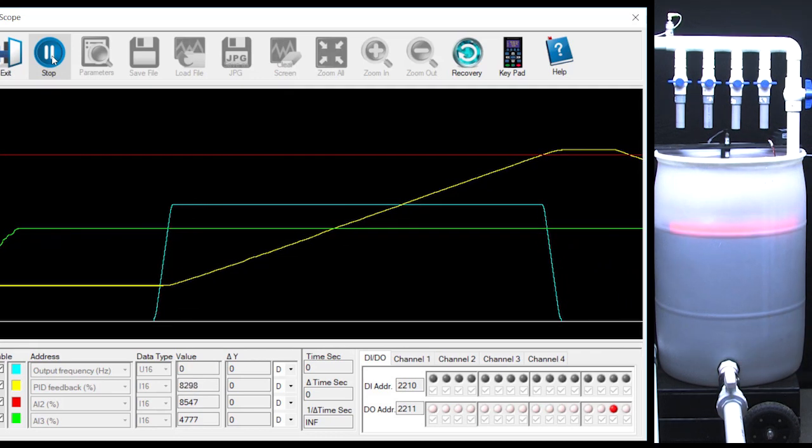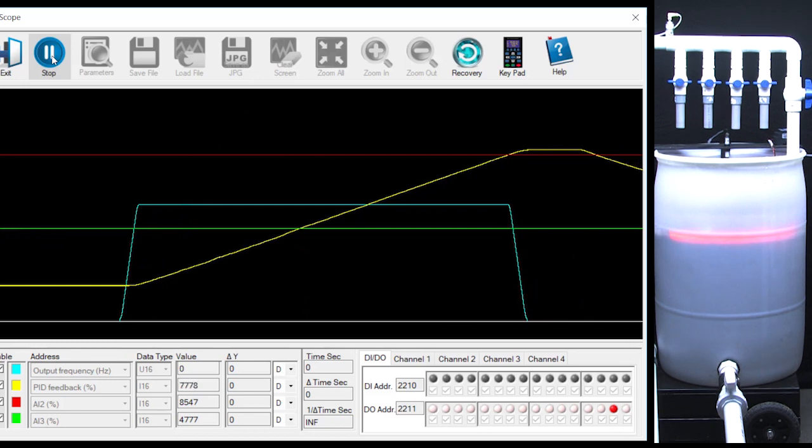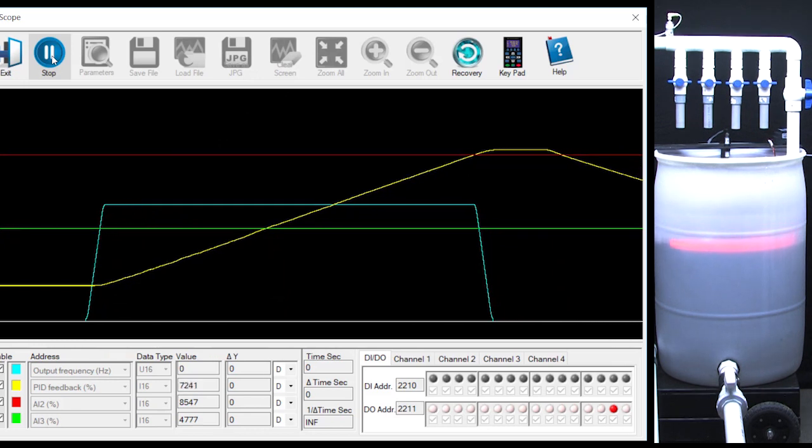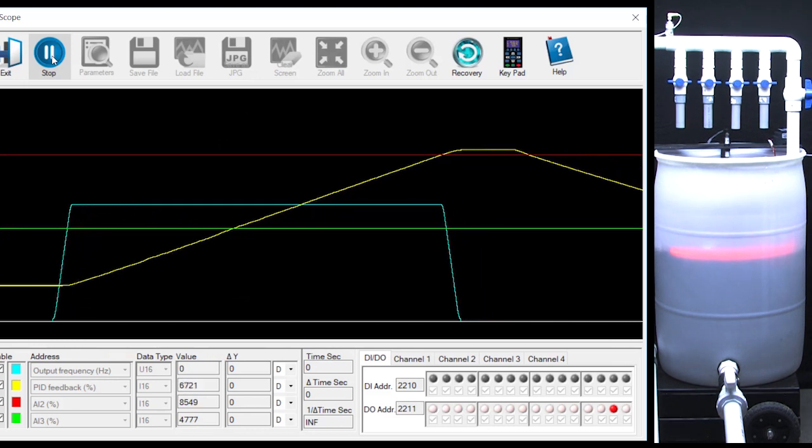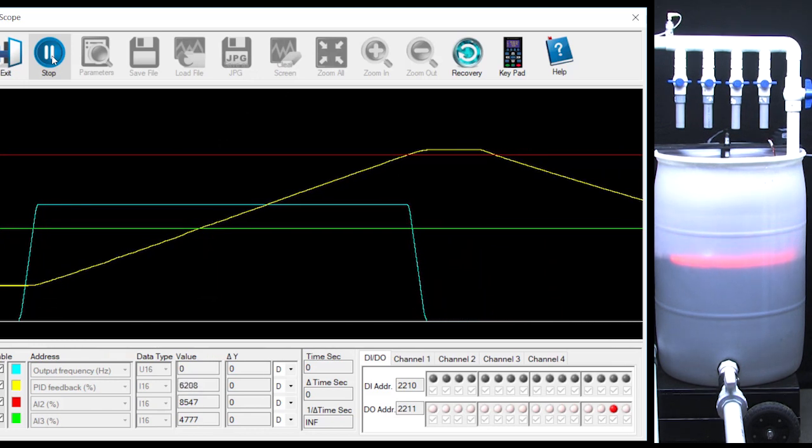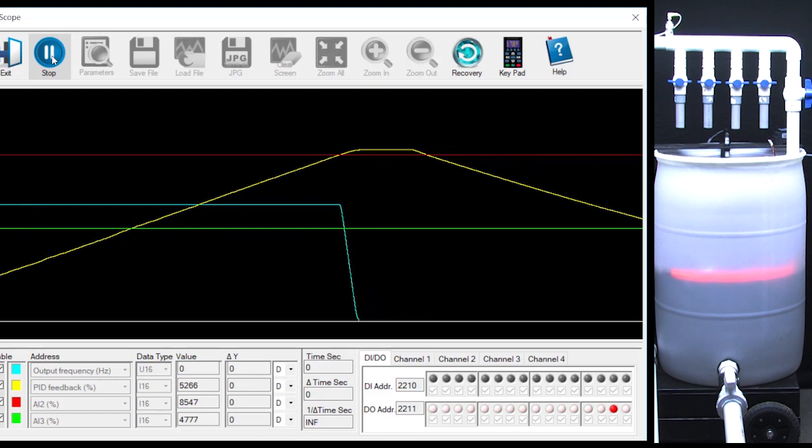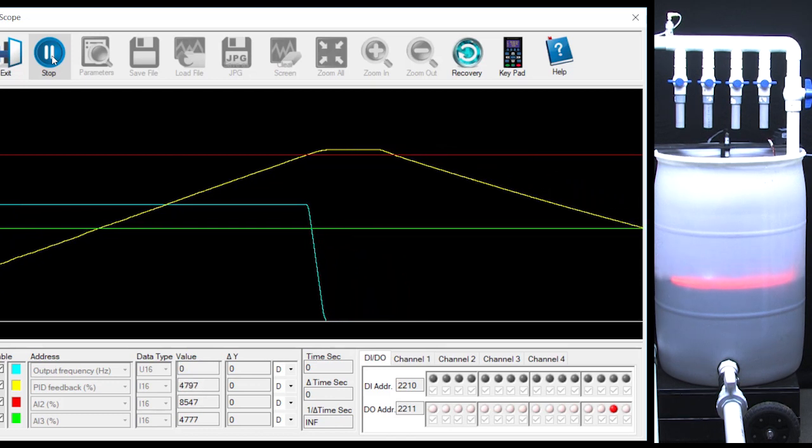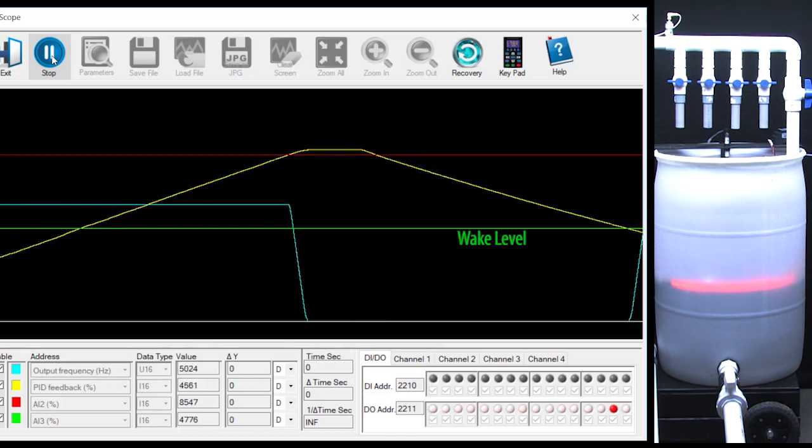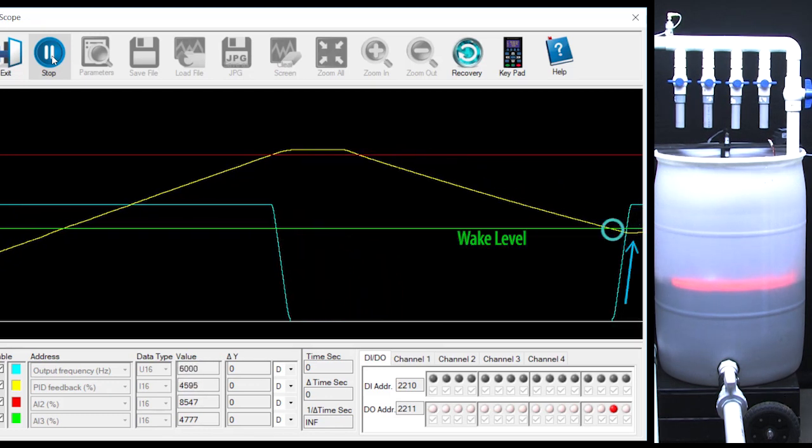Let's open the valve to simulate demand. We see the yellow process variable fall which tells us the water level is falling. When it hits the wake-up level, PID kicks in and cranks up the blue drive output frequency to fill the tank back up.